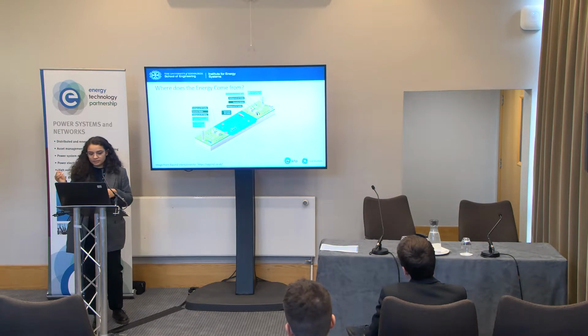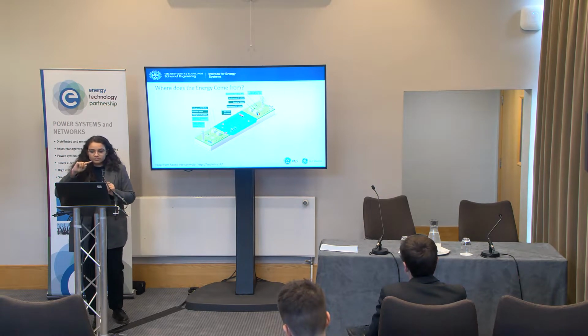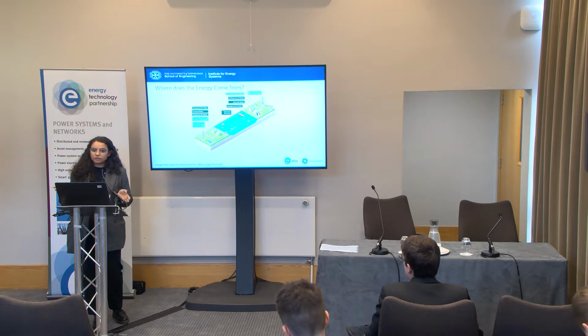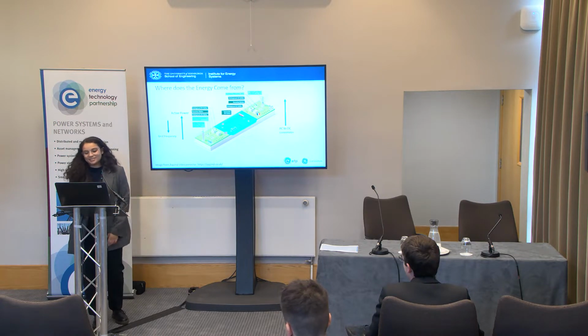So the idea was, what if for that little increase in power, we drain the energy in the converter, we drain the energy out of its capacitors and the cables if we have to, because we know that France has promised to increase the transmission across the DC link. So I simulated that many, many times. Oh, sorry, so the frequency has to go down and the active power has to go up. So what if the AC to DC conversion went up?